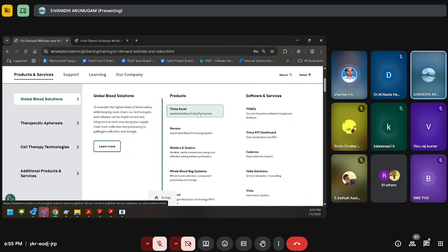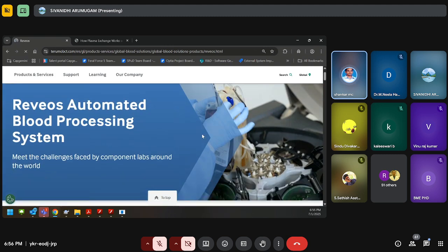Sorry, are there any further R&D related issues in that equipment, sir? R&D related? See, it again comes to us only. So we are working in R&D, right? For example, in some regions like Japan, during winters, this tubing set, I mentioned the cassette, becomes frozen. So they said they want some cooling period, or some heat time, or more temperature. Those minor changes they expect from the R&D team, that is from us.